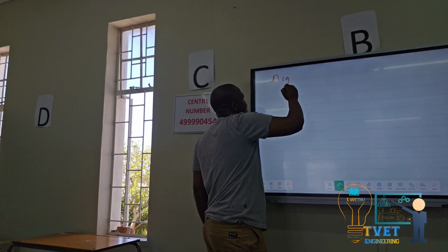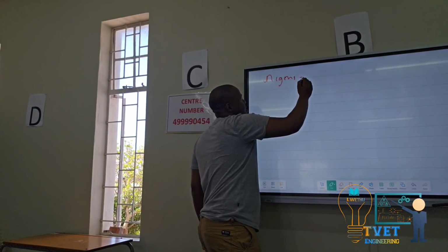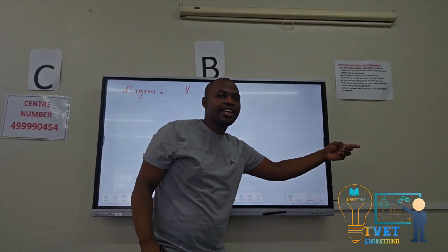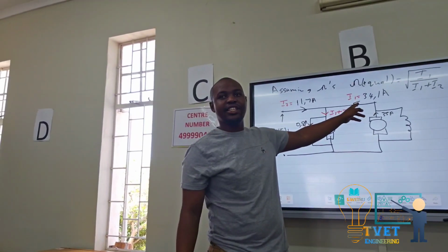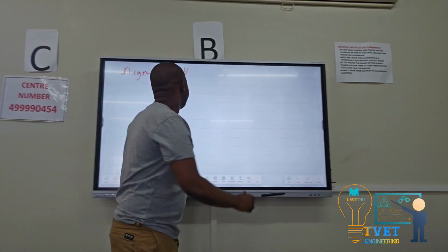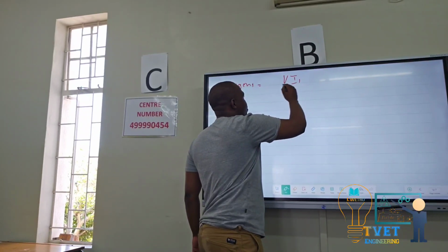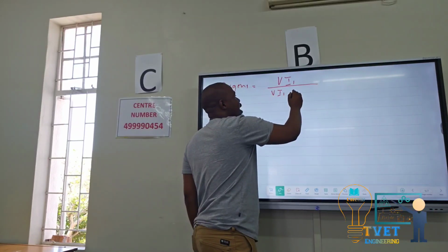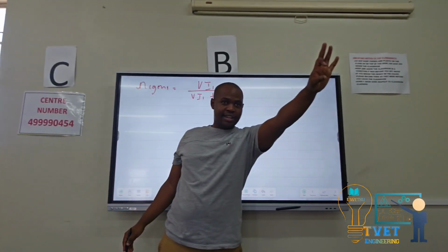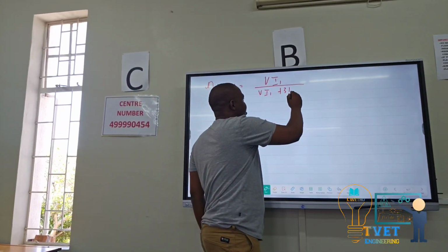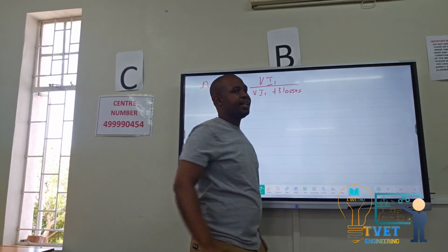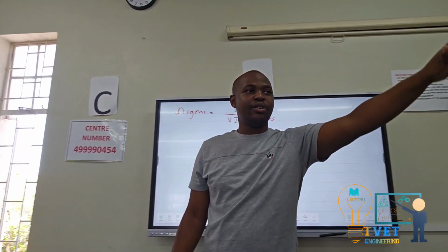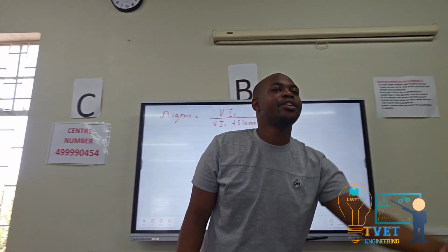The efficiency of the generator is equal to V times I1, the load current or output current of the generator, over V times I1 plus the losses. There are 3 losses, which are the armature copper loss, the field copper loss, and lastly the iron and friction loss.